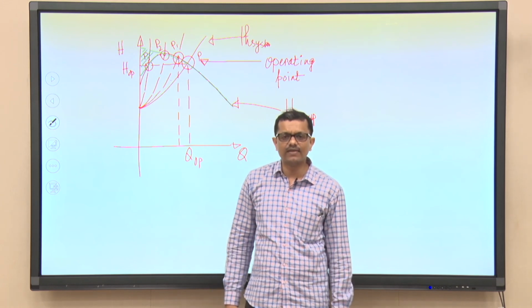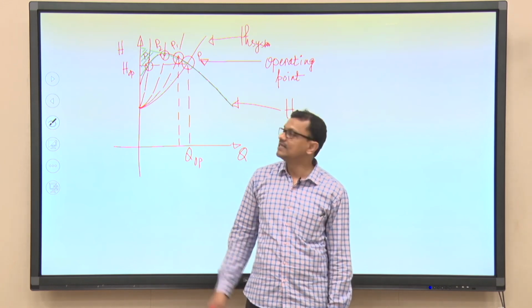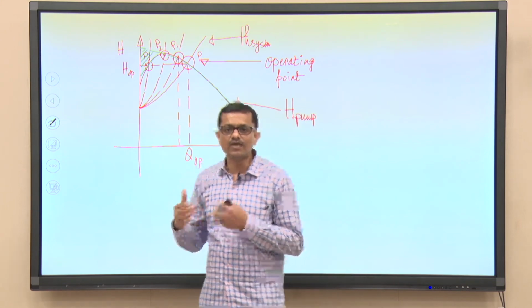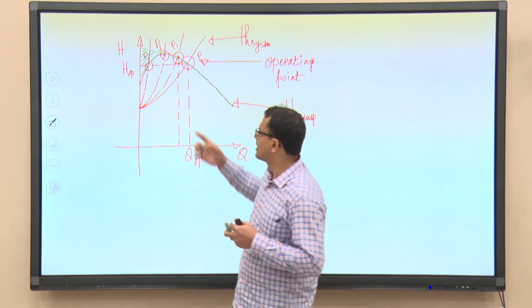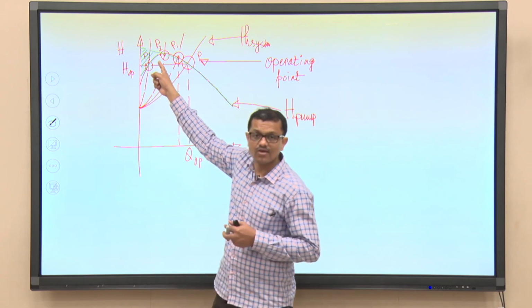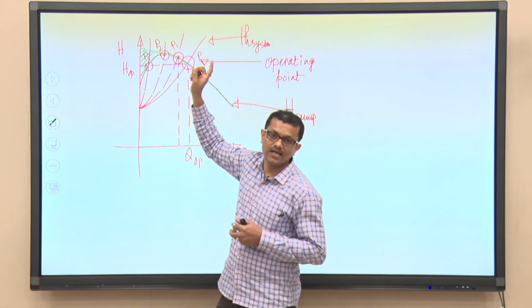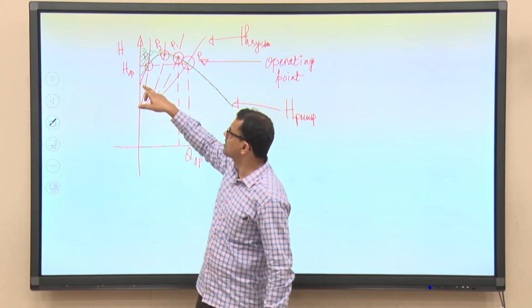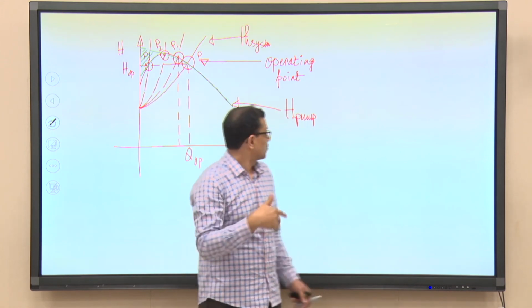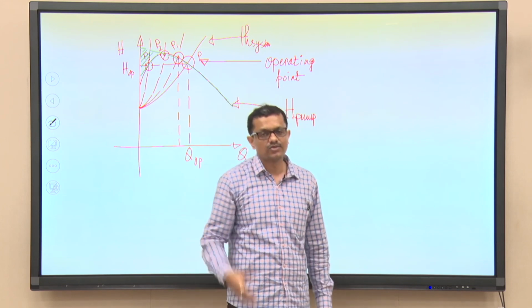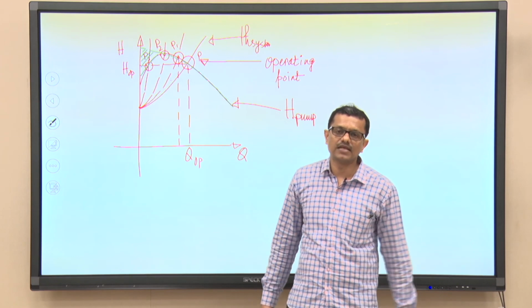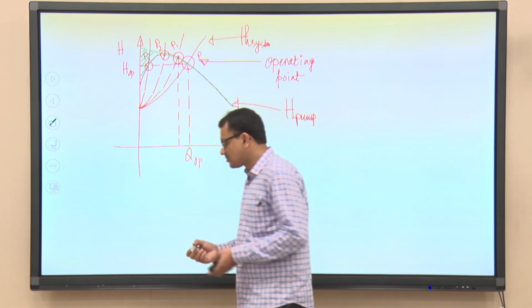We really cannot eliminate it, but our objective should be that whenever a pump designer designs a pump, he or she should keep in mind that the losses due to separation of flow at the pump suction side should be minimum, so that instead of having the pump characteristics curve like this, we should have a continuously drooping characteristic, so that the problems that we have discussed can be eliminated, okay.